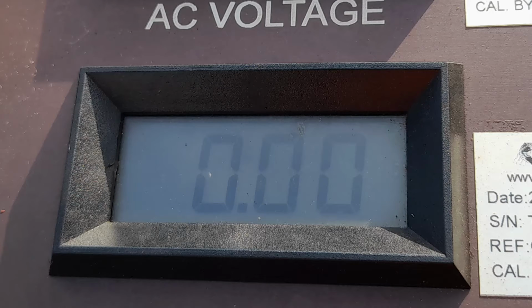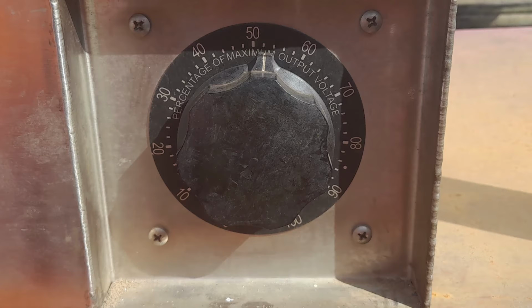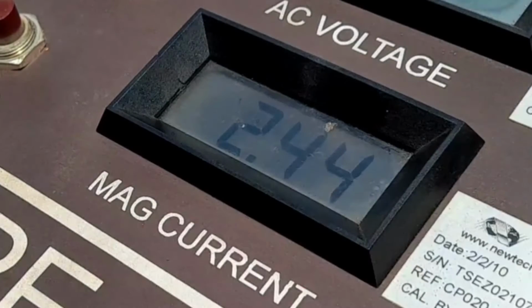Power on the machine, switch on the coil, then it will show the connection is okay, it will show the ampere. If the ampere is not showing, you have to check the variac; it will be 0. So then move the mag control forward, then increase the mag current, and it will show the ampere. When the ampere is showing, the connection is okay. If the connection is loosened or you didn't connect properly, then the ampere will not show and the mag will not be switched on. These are the basic troubleshooting techniques. If the mag is on, the ampere will show and the magnetic field will be there.